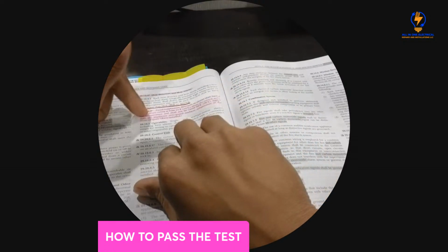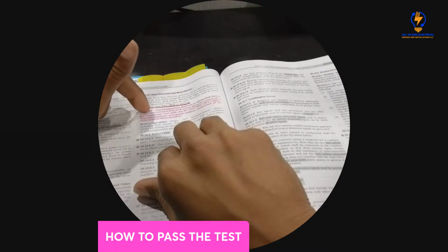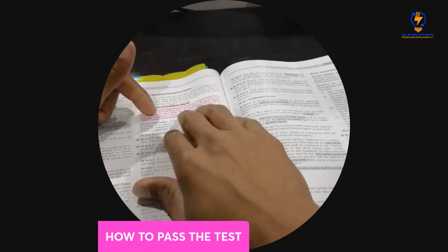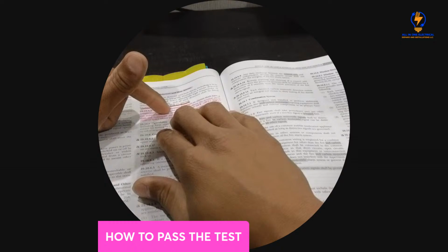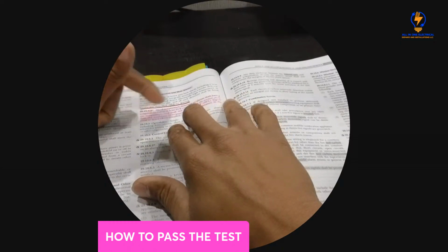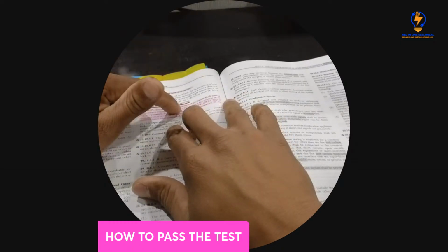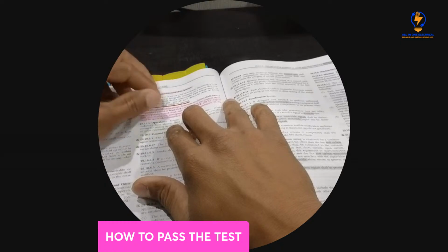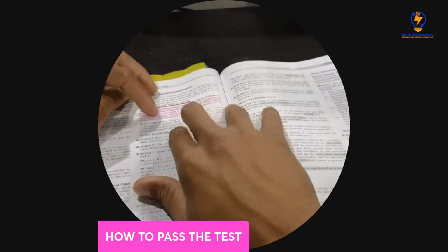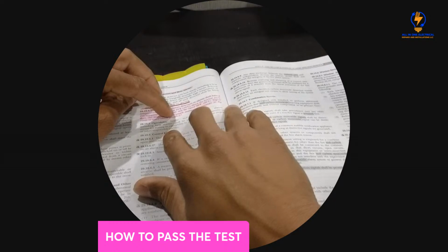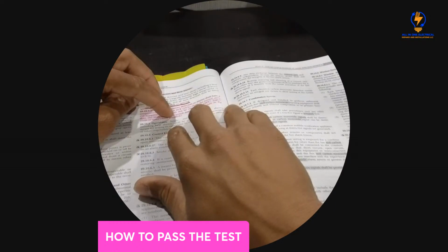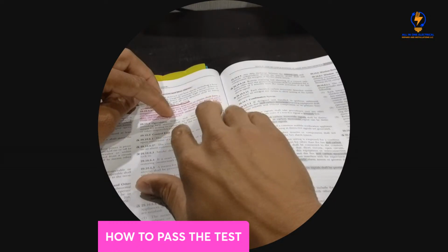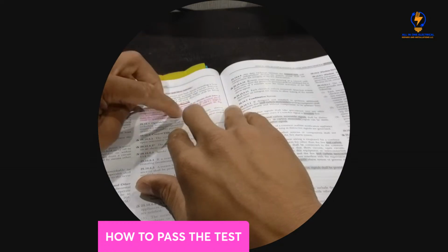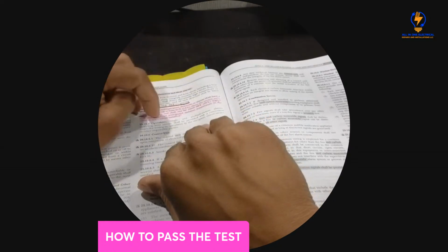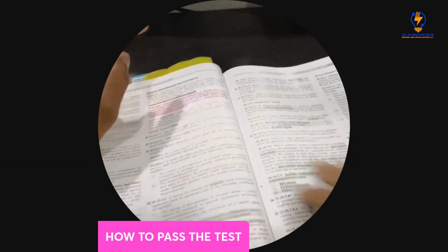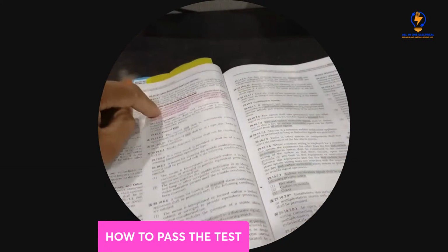And then right here, 29.10.4.2, which is fixed temperature detectors or alarms shall be temperature rating at least 25 Fahrenheit, 14 Celsius above normal ambient temperature and shall not be rated 50 Fahrenheit or 28 Celsius higher than the maximum anticipated ambient temperature in the room or space where installed. Very important, it is in red that I highlight here.